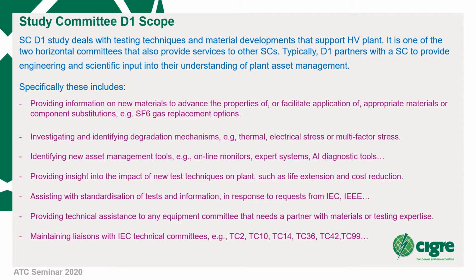Our work in the materials area covers gaseous, liquid, and solid materials. We continue to work on traditional materials such as SF6, mineral oils, epoxy resins, and XLPE, but also on development of new materials such as SF6 replacement gases, vegetable oils for power transformer insulation, and nanopolymer composites for insulator applications. We investigate properties such as dielectric strength, thermal conductivity, aging properties, resistance to partial discharge, and performance under different voltage stresses such as AC, DC, impulse voltages, and combinations of them.